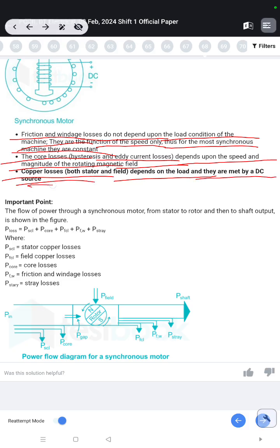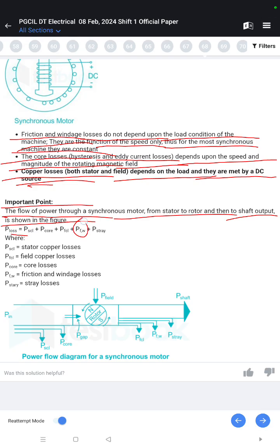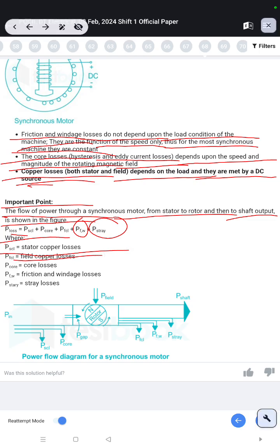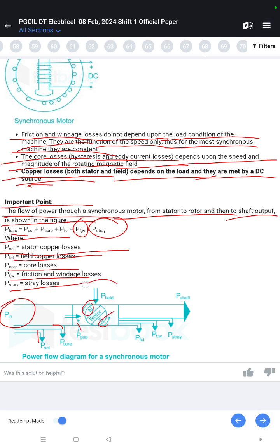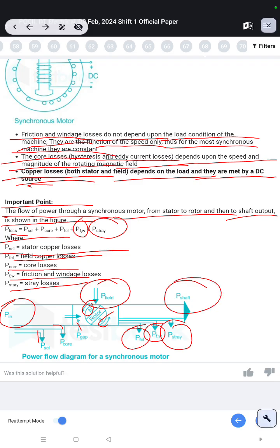Important point: the flow of power through a synchronous motor from stator to rotor and then to shaft output is shown in the figure. P loss = PSCL + P core + PFCL + PFW + P stray. Here PSCL is stator copper loss, PFCL field copper losses, P core core losses, PFW friction and windage losses, P stray stray losses. P in, PSCL, P core, then P gap, then rotor, then P field, then PFCL, PFW, P stray, P shaft. Power flow diagram for a synchronous motor.